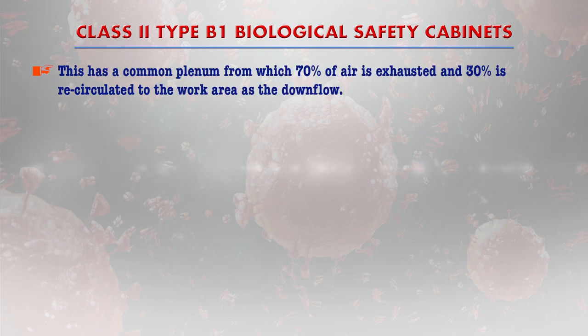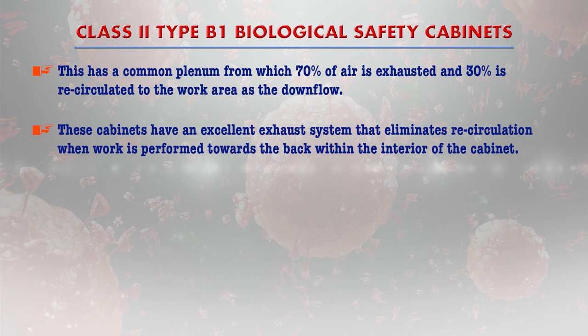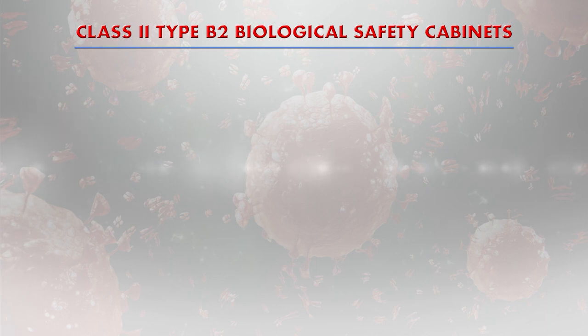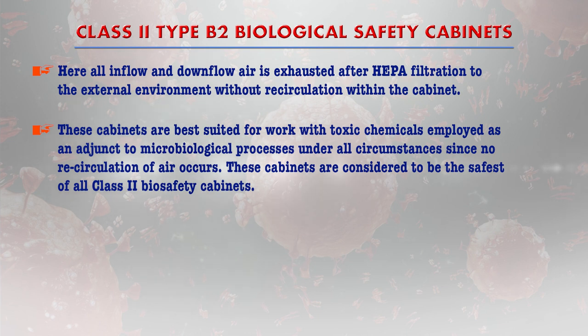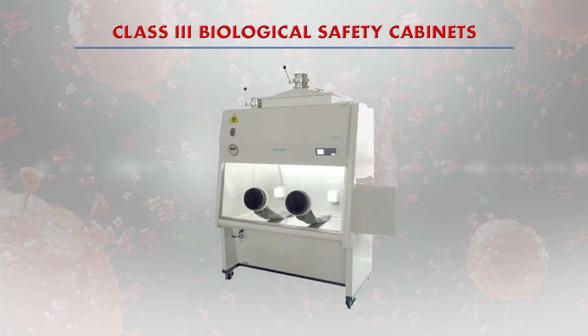The class 2 type B1 biosafety cabinet has a common plenum from which 70% of the air is exhausted and 30% is recirculated to the work area as downflow. These cabinets have an excellent exhaust system that eliminates recirculation when work is performed towards the back of the cabinet interior. In class 2 type B2 biosafety cabinets, all inflow and downflow air is exhausted after HEPA filtration to the external environment without any recirculation within the cabinet, making them best suited for work with toxic chemicals used alongside microbiological processes.